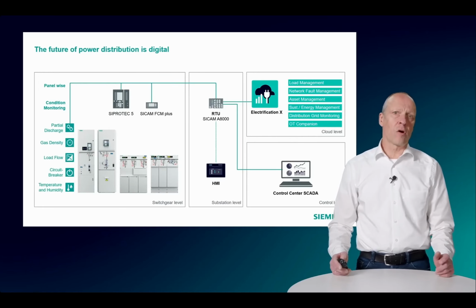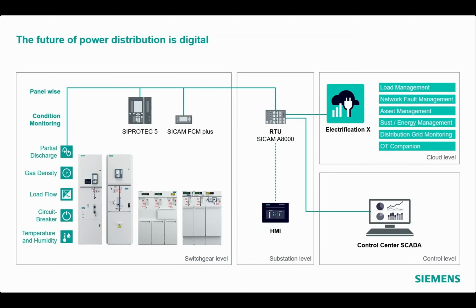If we have a look on the architecture of our end-to-end monitoring solution, we have either in the switchgear or the substation level one centralized gateway from our SICAM A8000 RTU family. It collects all the sensor information either directly from the sensors or from intelligent devices like the SIPROTEC 5 protection relay or the SICAM FCM plus fault indicator. Those monitoring functionalities are available either on-premise with a local HMI, in SCADA, or as a cloud-based IoT application, like the different feature sets of our Electrification X.